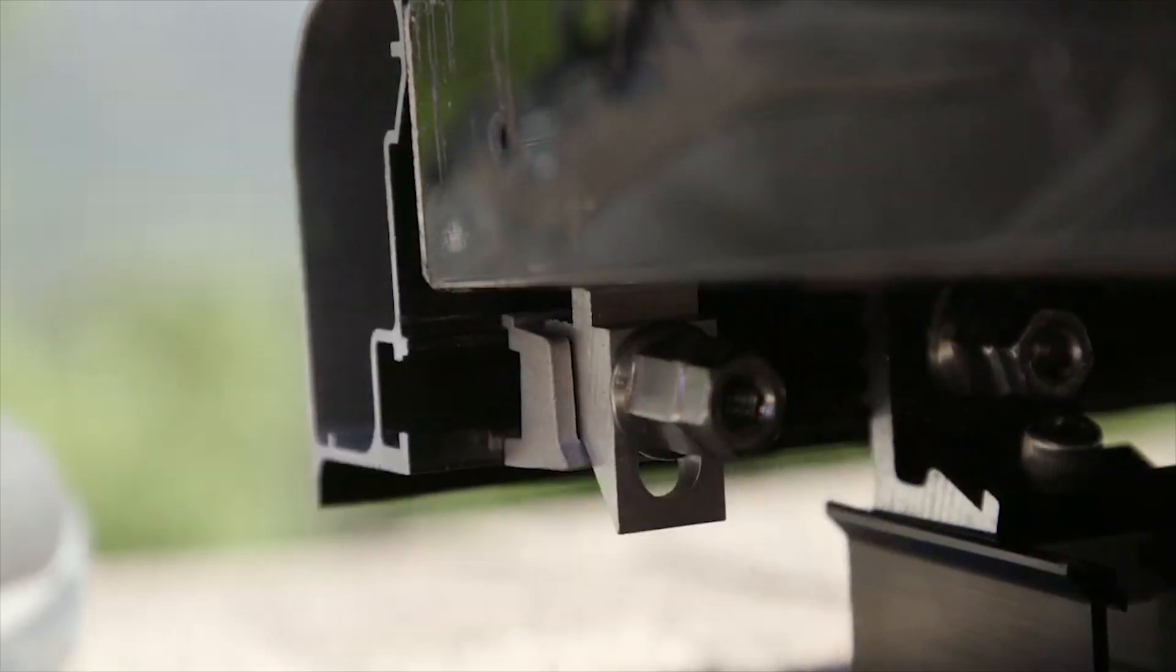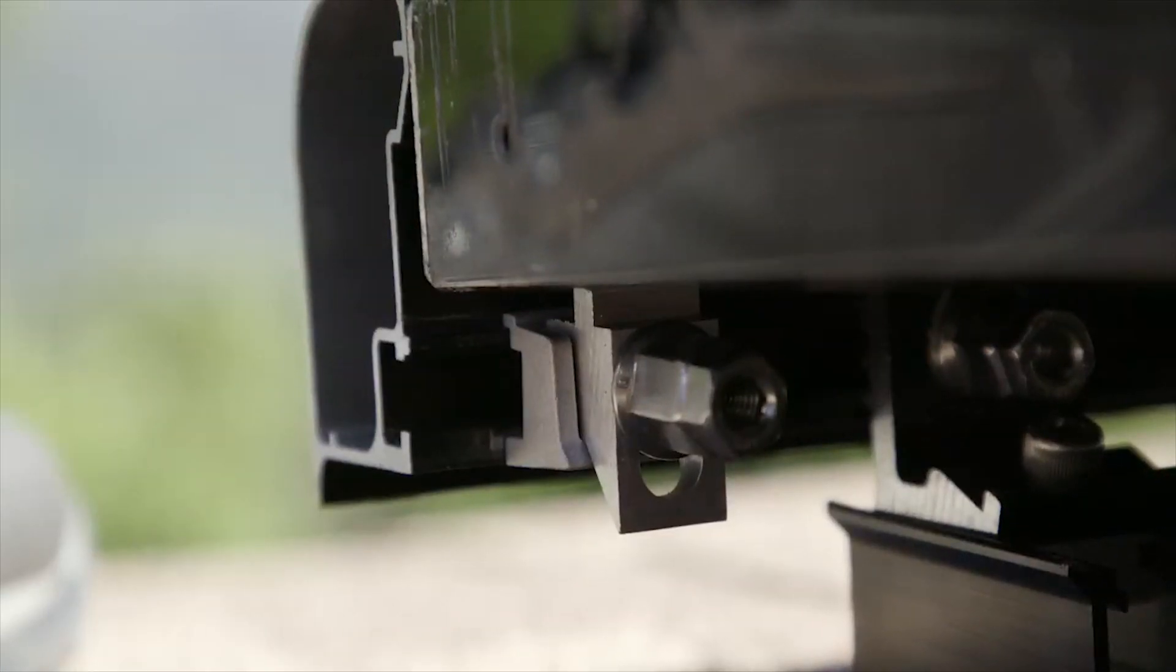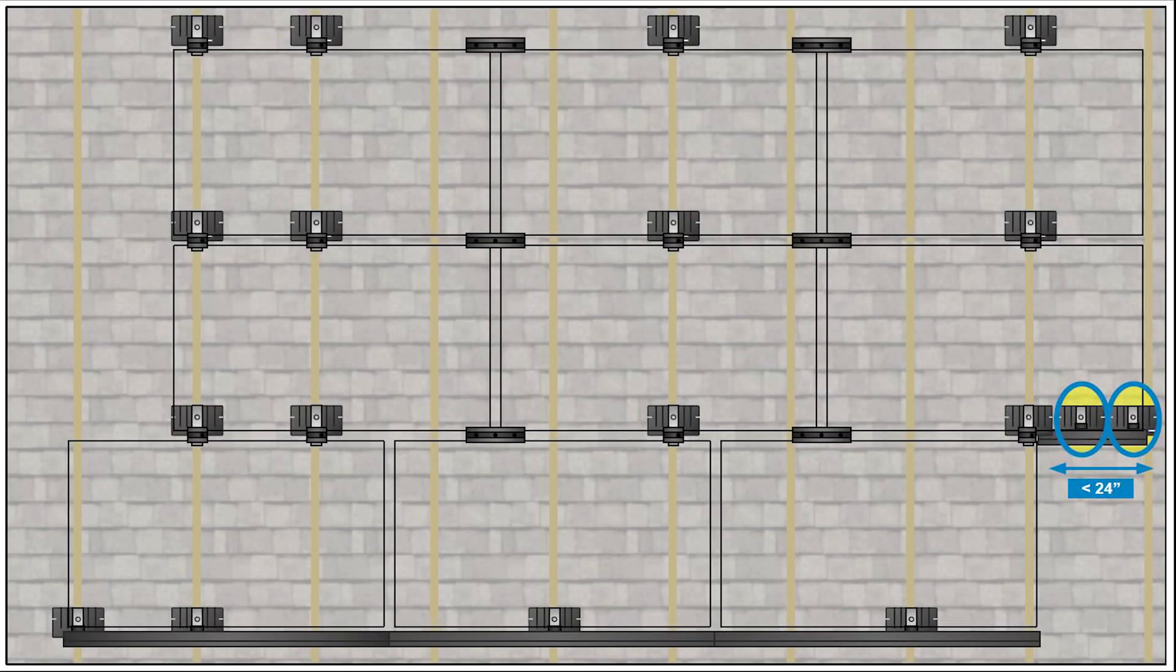To use a trim clamp, install the modules, then insert the trim clamp into the trim rail slot and tighten the nut to 20 foot-pounds using a quarter-inch hex tool.